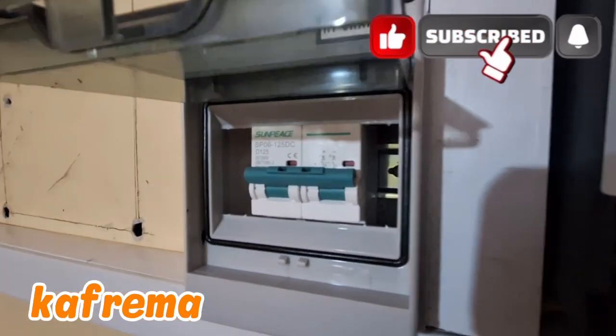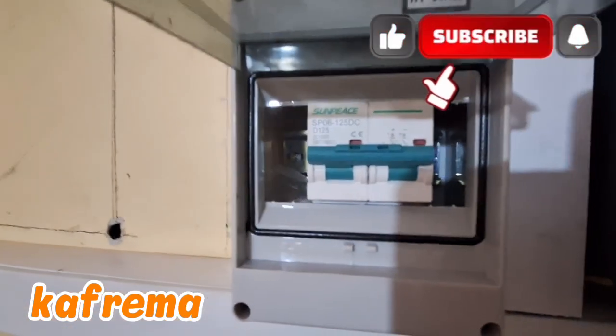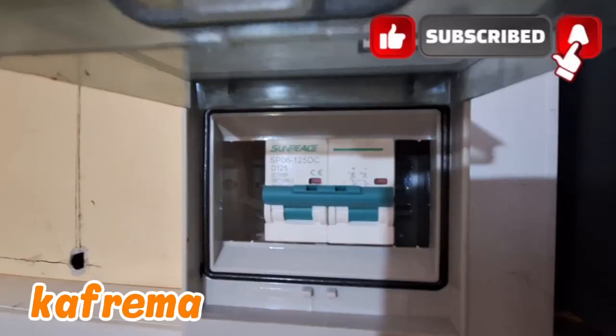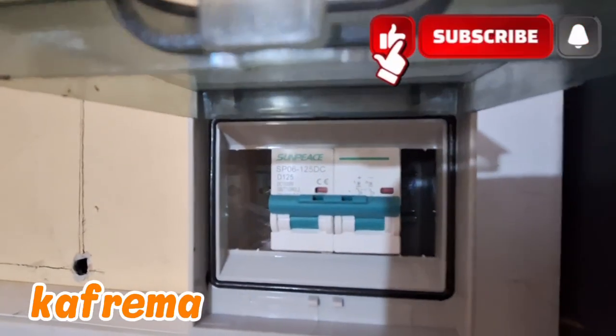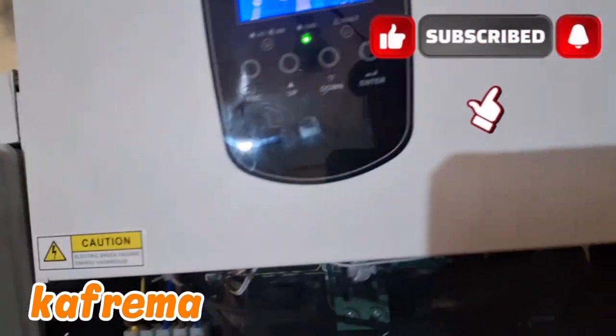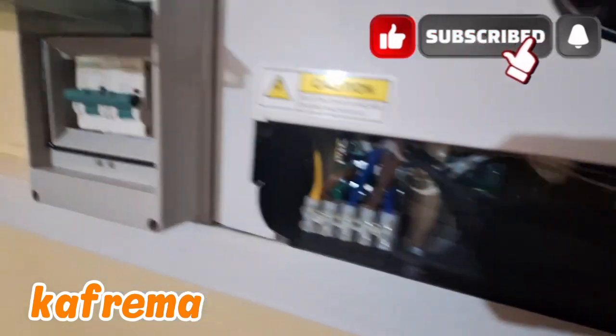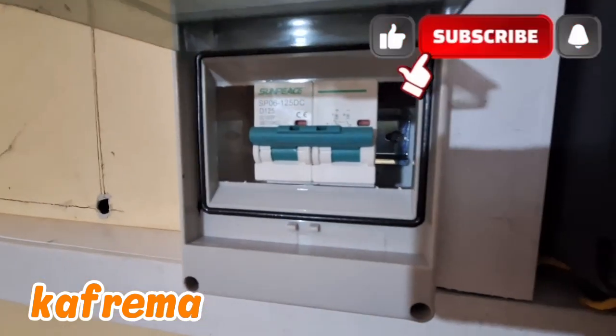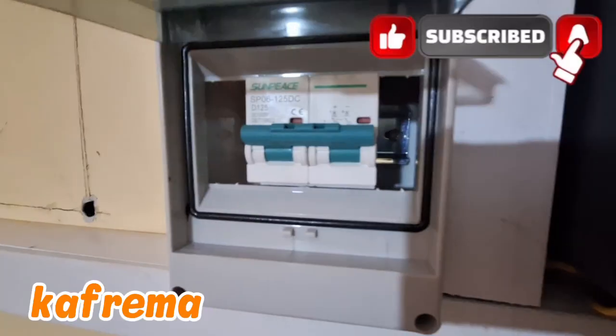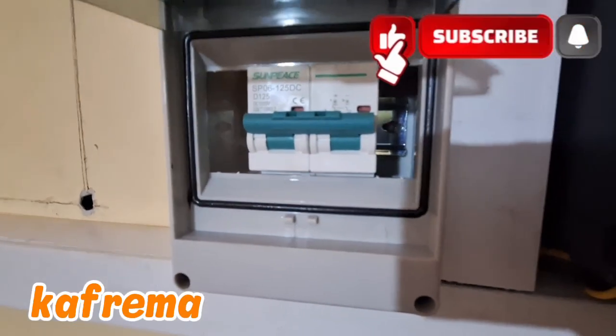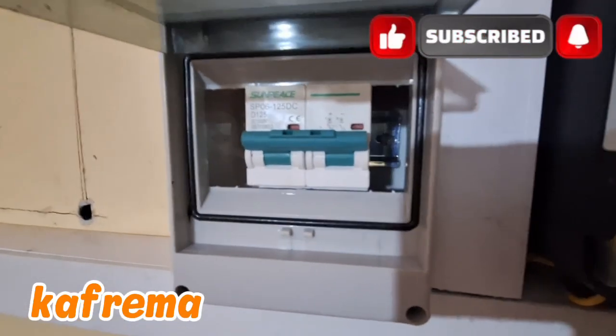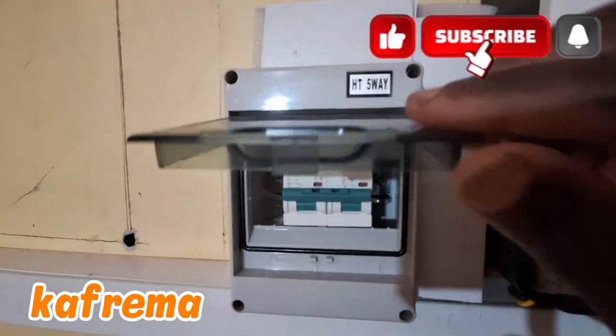This is a bus bar, positive here, negative here. Through this trunk there are wires inside. This is the circuit breaker to the battery bank, 125, because our inverter is 3 kVA. This is a 3 kVA inverter, so we have to protect it using 125. That is 3000 divided by 24 volts. You see, it's about 125 amperes. That's why we have this circuit breaker here.